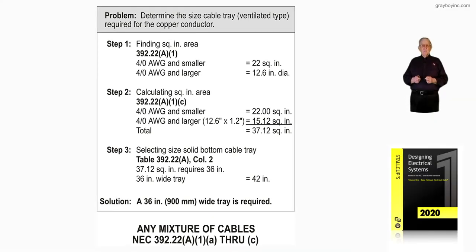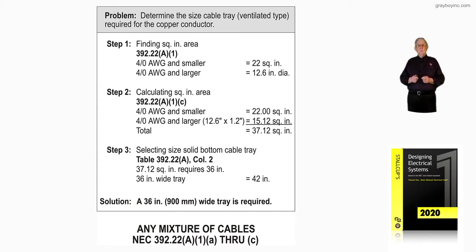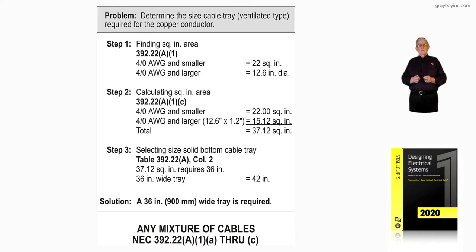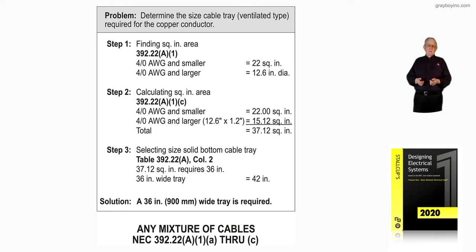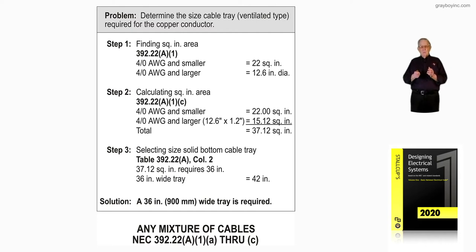This illustration shows the calculation of a mixture of cables in accordance with 392.22A1A to A1C. The problem is we want to determine the size of the cable tray — ventilated type. You have to know the type of cable tray: is it a ventilated bottom, ladder type, or is it a totally closed bottom? In this case, it's the ventilated type.